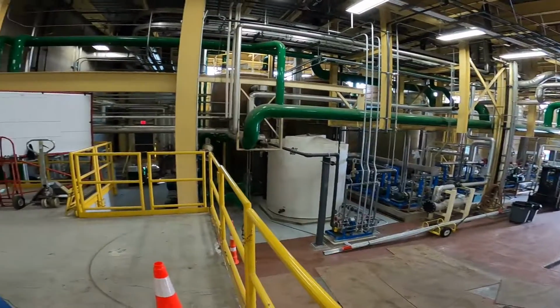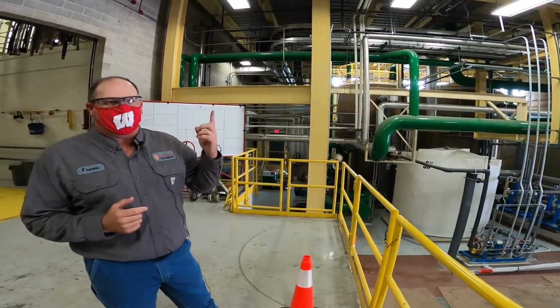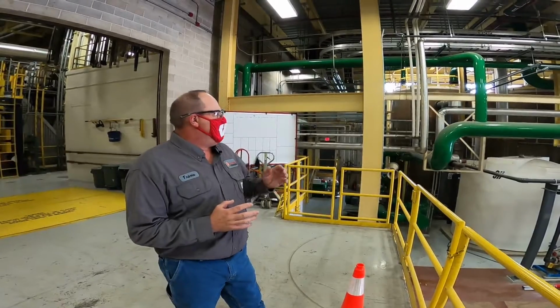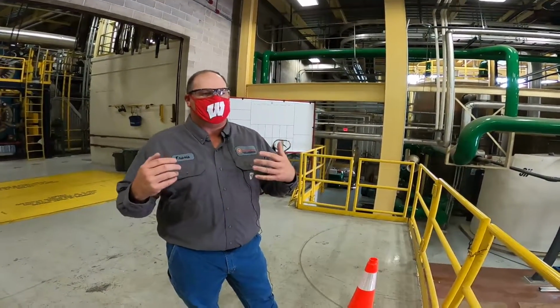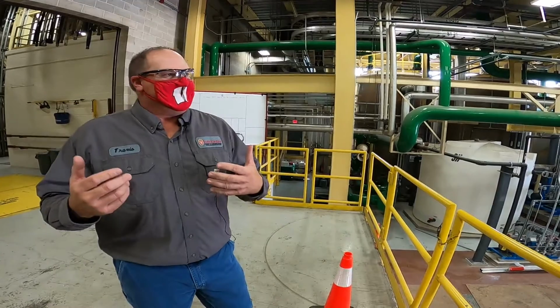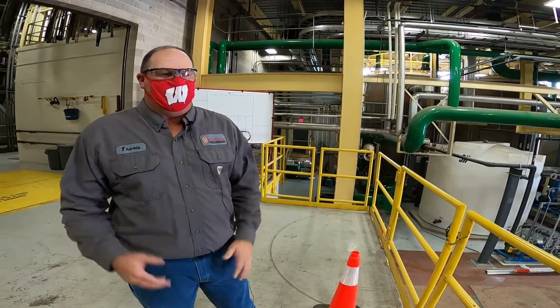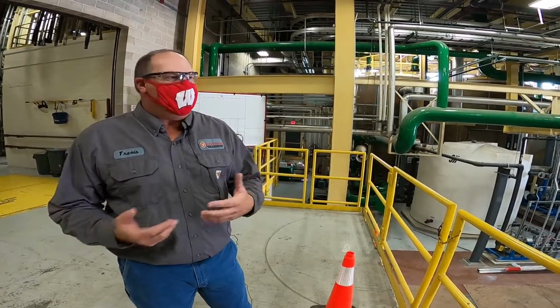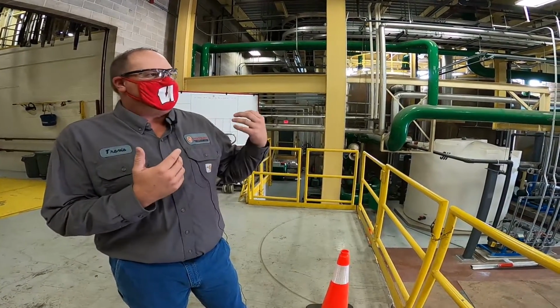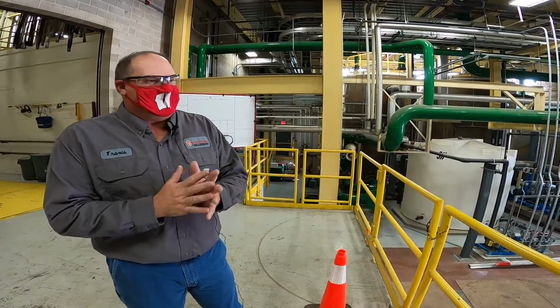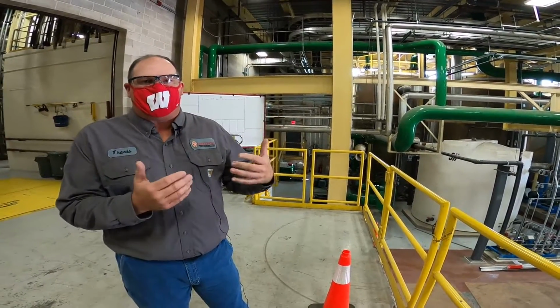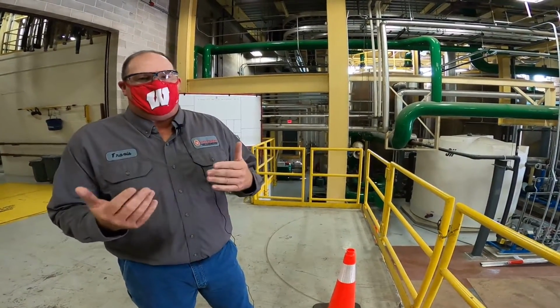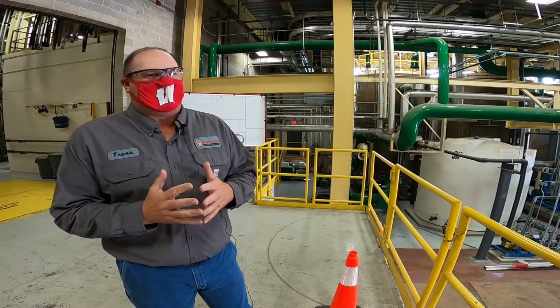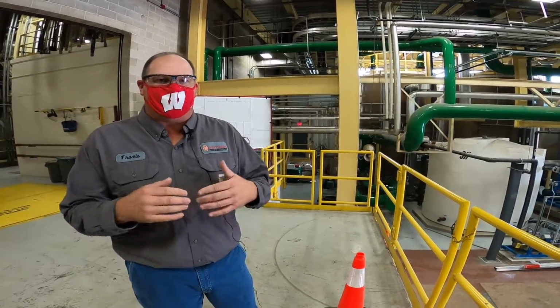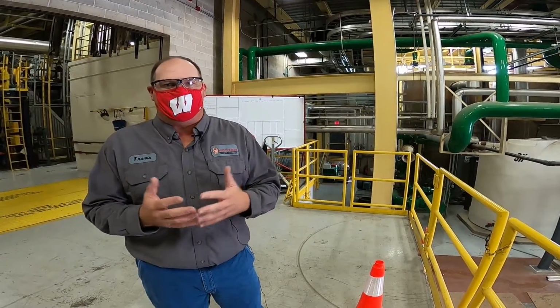It's for boiler makeup water, cooling tower water for the chiller system, and what we call closed loop cooling, which is just used to cool the turbine equipment in the plant, to keep all the equipment cool, just like your car with a radiator. We got to do the same thing here, so we actually use the lake water for that system. If the lake water system fails, our backup is city water. City water being quite a bit more expensive, about $5 for every 1,000 gallons. Lake water is about 50 cents for every 1,000 gallons.